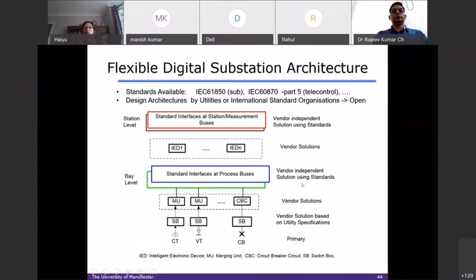Basically for utility design - in this case I designed this for the national grid, with blue, red, and green. We did this differently because to have that reliability we used a double bus. Then you have a station bus and measurement bus, which I'll talk about later. Then we select a vendor solution, which basically uses the vendor's equipment, all based on the standard IEC 61850.